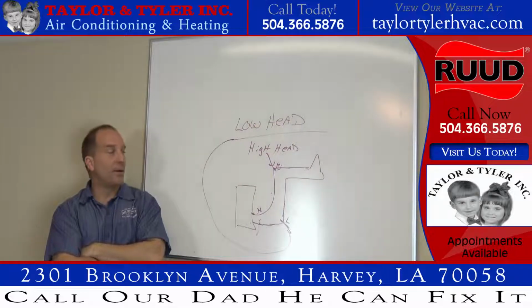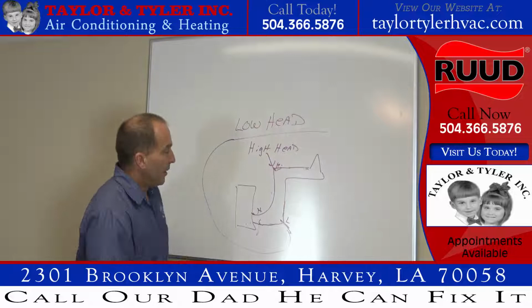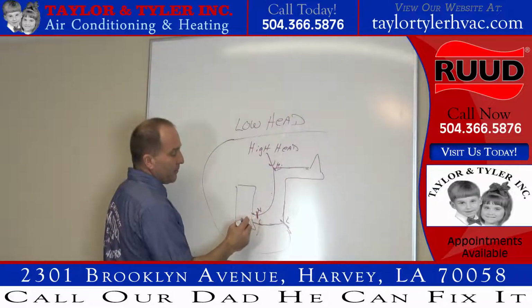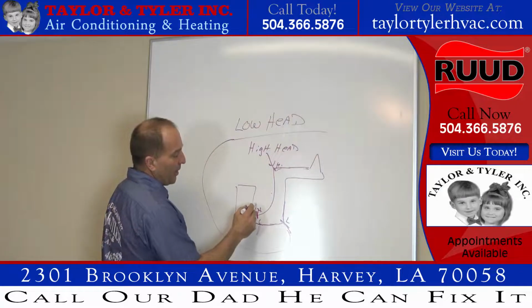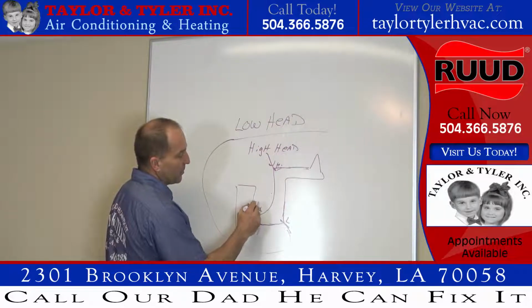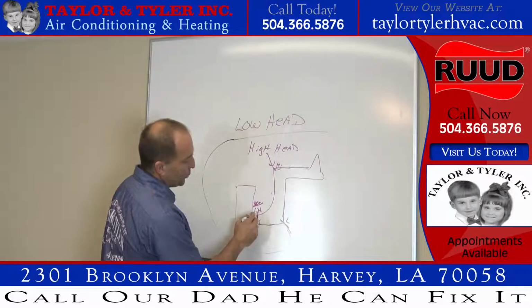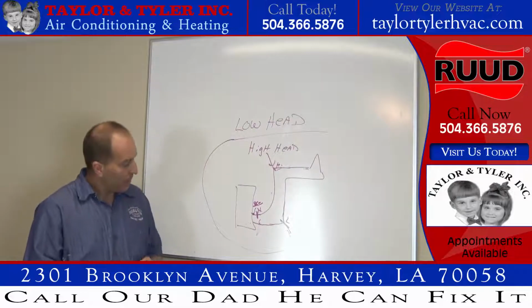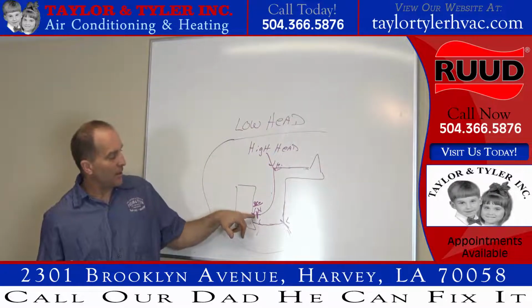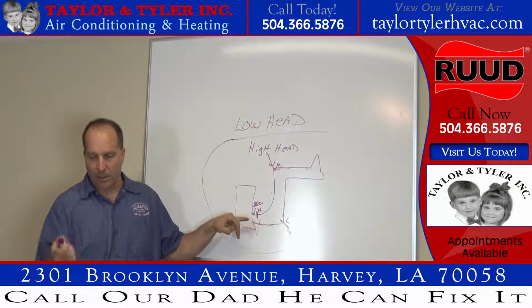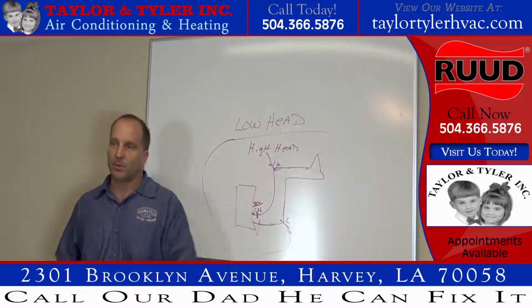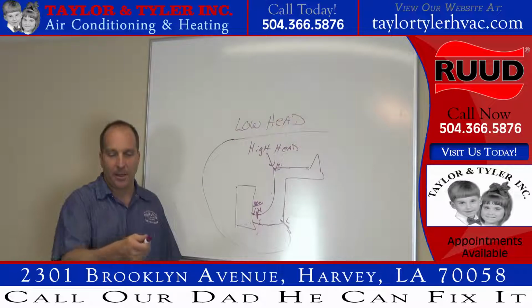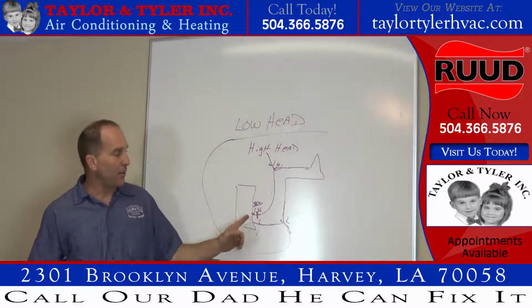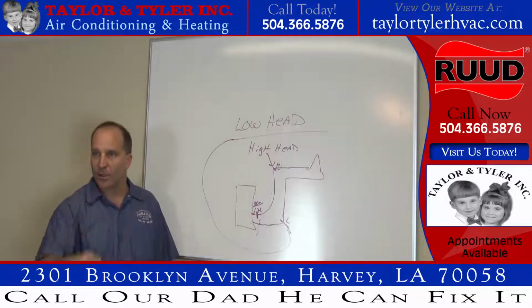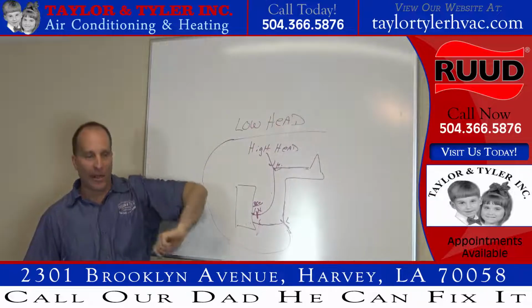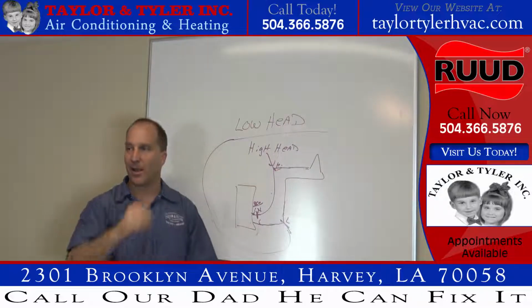Okay, well let me wrap your head around it real quick. If my kink is here, and I got a gauge sitting right here, and I'm reading my high side right here, and let's just say it's 350 pounds. If I get a restriction right by my gauge, then as soon as that refrigerant comes out, and let's just say I got a shutoff valve there, so I can simulate a restriction, okay? So I go ahead and I kink it down, and I restrict it, my head pressure, as soon as I start restricting it down, goes skyrocketing up, right? I open it back up, boom, head pressure comes back down, right?